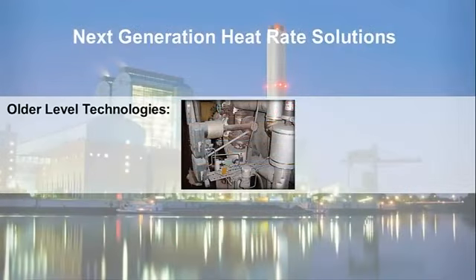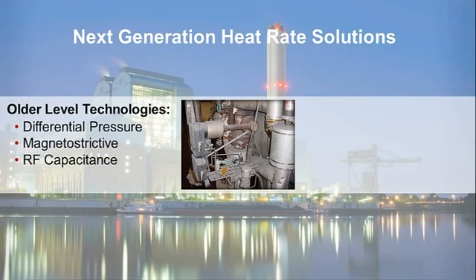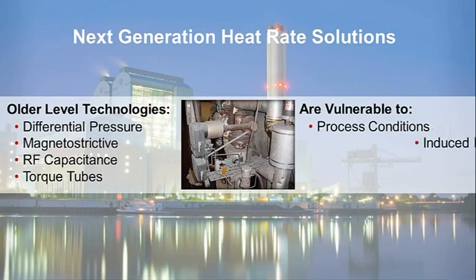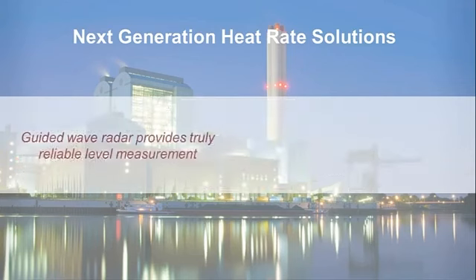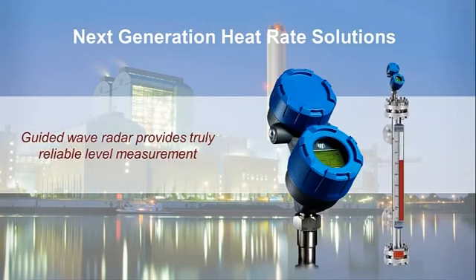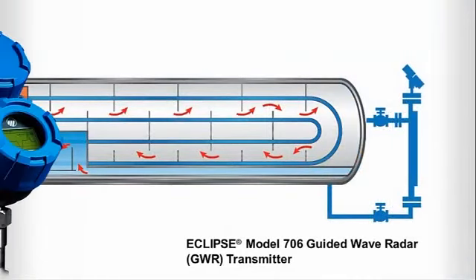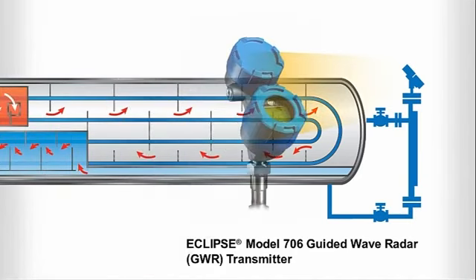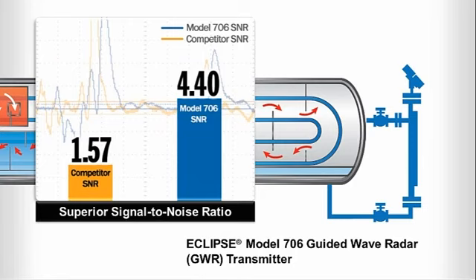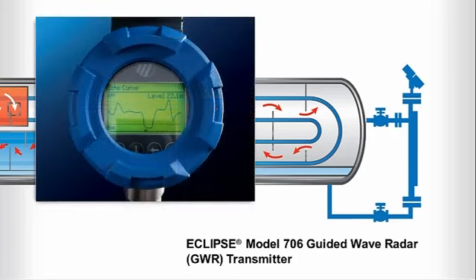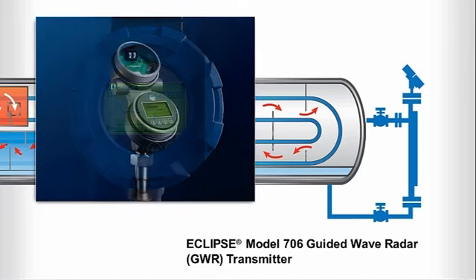Older level technologies, such as differential pressure, magnetostrictive, RF capacitance, and torque tubes, are vulnerable to process conditions and induced instrument errors, such as shifts in specific gravity and mechanical or electronic drift. In contrast, guided wave radar provides a truly reliable level measurement solution for feed water heaters. Magnetrol's new Eclipse Model 706 provides enhanced guided wave radar performance, virtually unaffected by process variations. The Eclipse Model 706 gives you a superior degree of accurate and reliable continuous level measurement without the need for calibration or gravity corrections. By combining superior signal performance and advanced diagnostics, the Eclipse Model 706 delivers premier level control for feed water heaters, as well as a broad range of challenging applications such as condenser hot wells, de-aerators, and cooling tower basins.